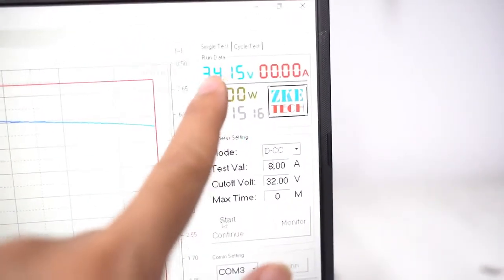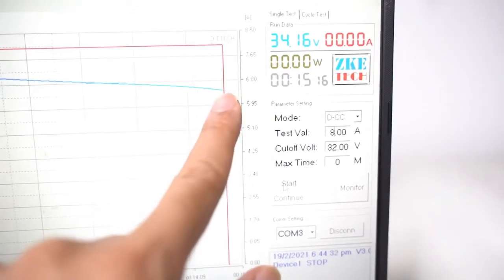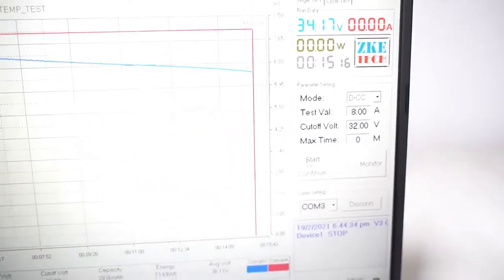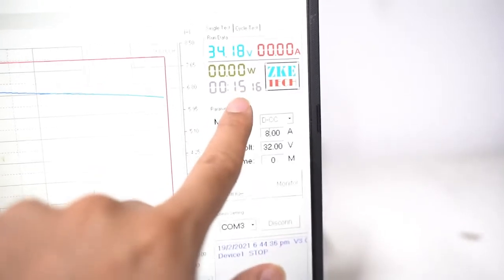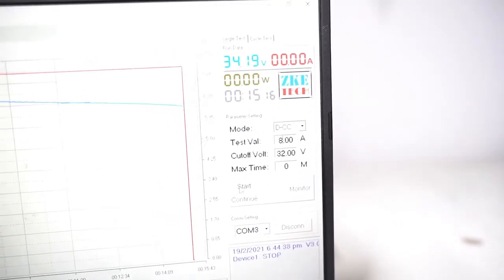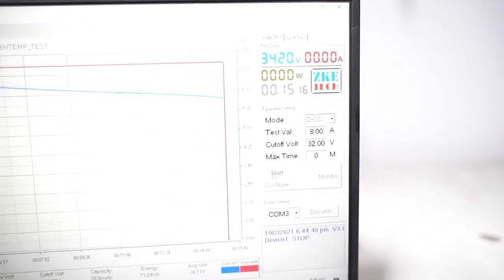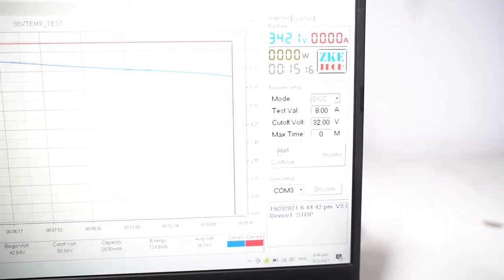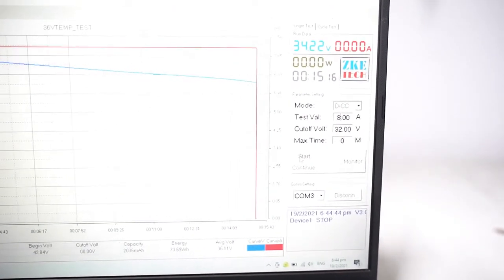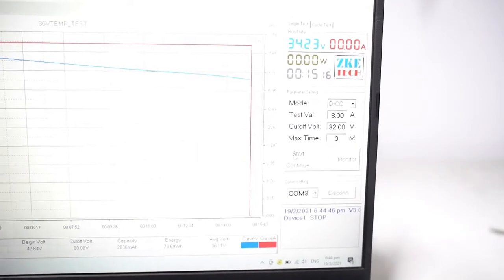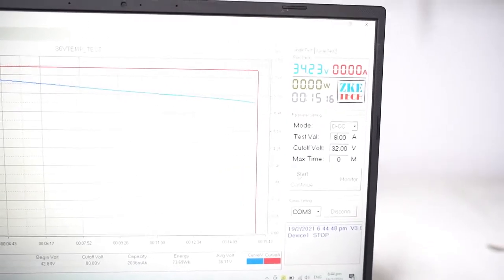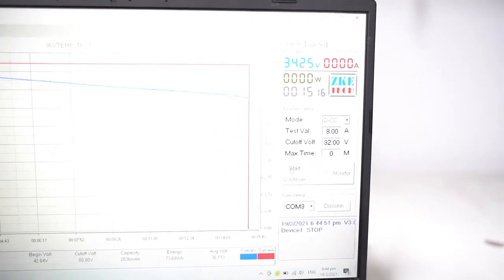It is at 34.15 at the lowest cutoff point with a discharge of 15 minutes and 16 seconds. That's pretty good. We started out at 42.9, I think. And now we're at 34.2, so that's a pretty good discharge curve.